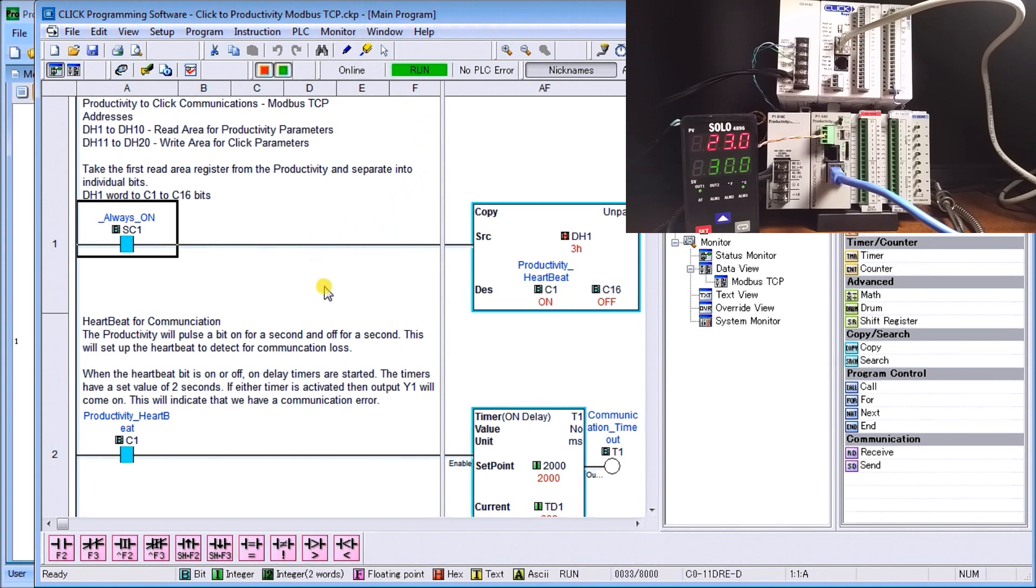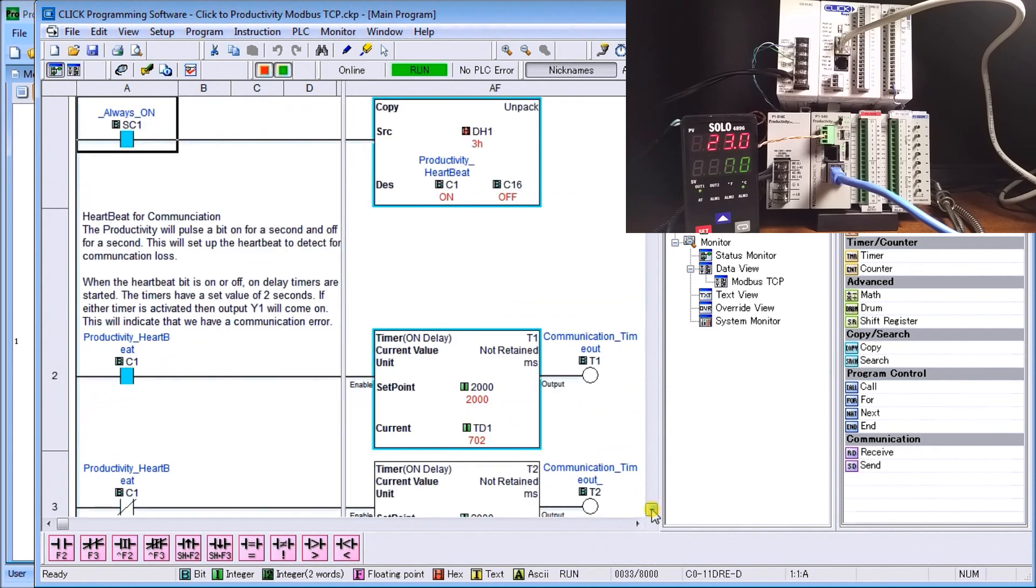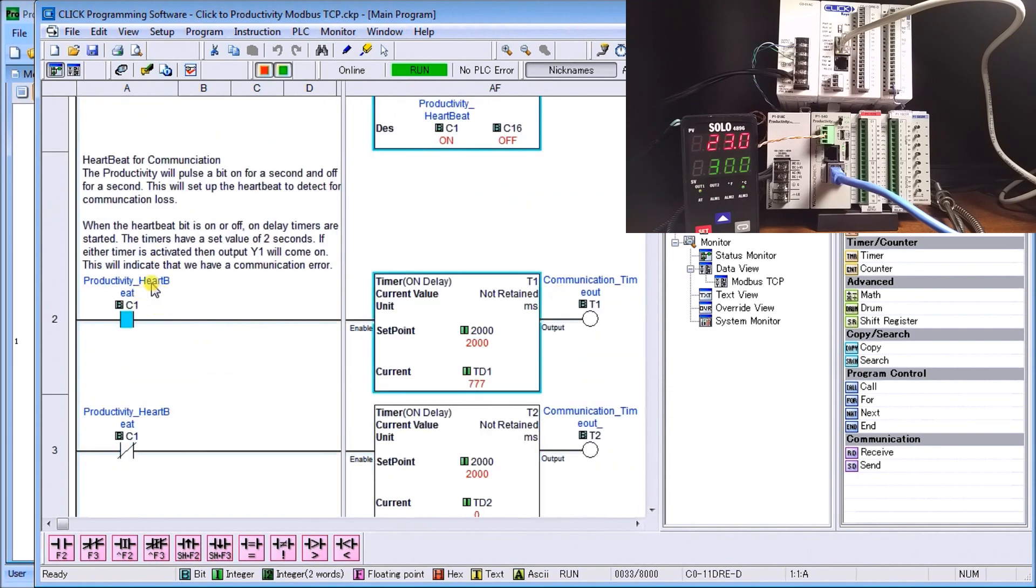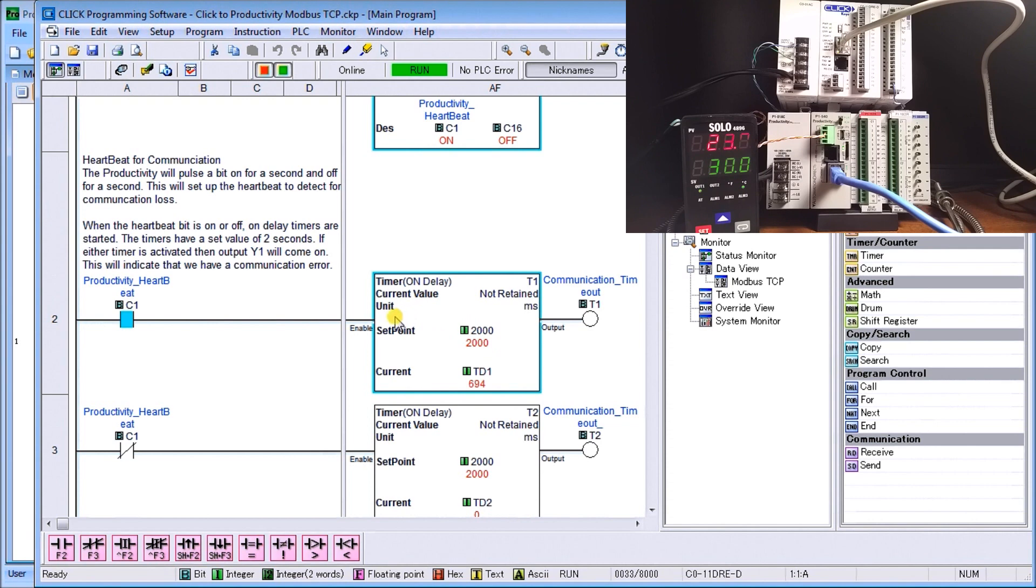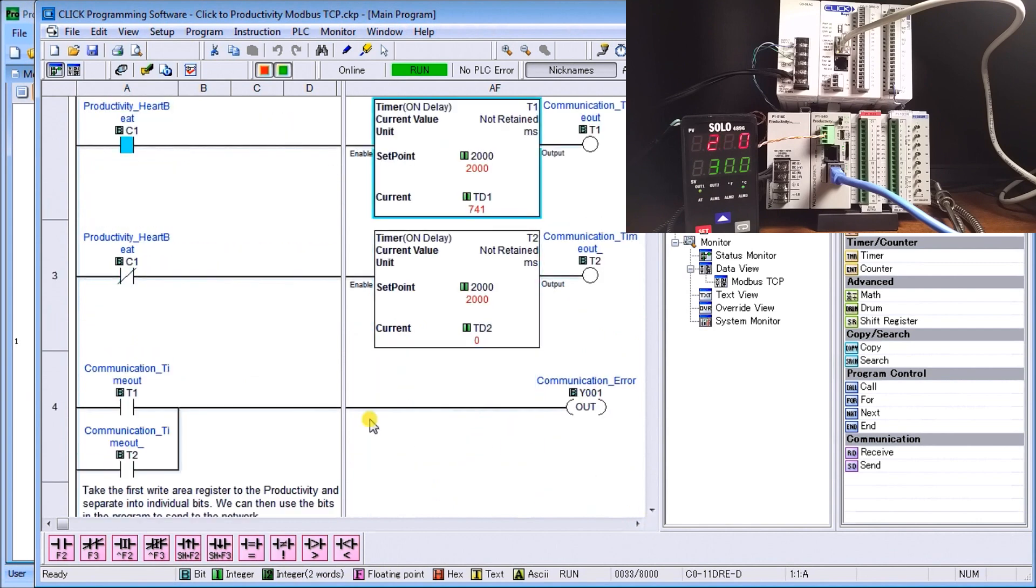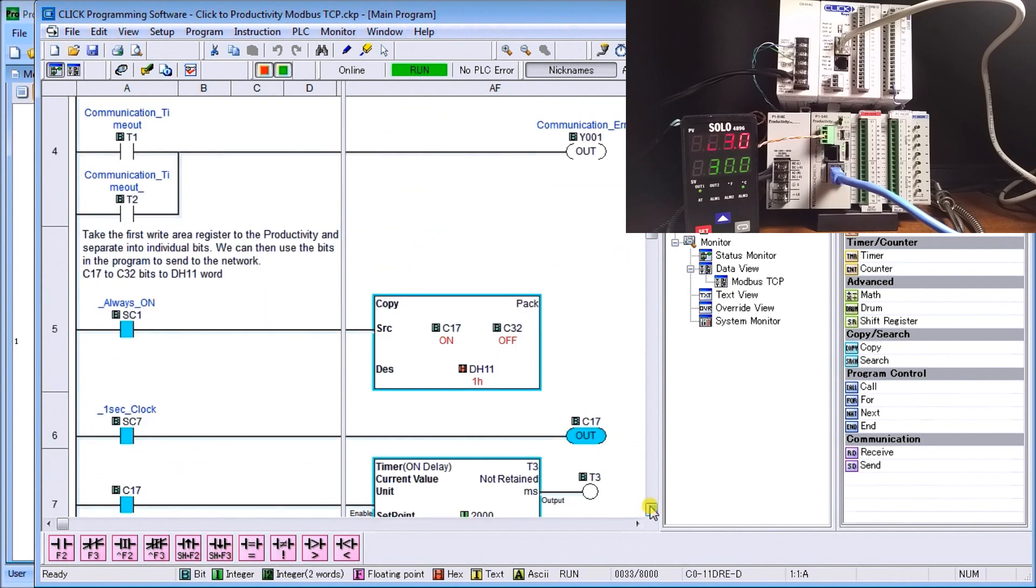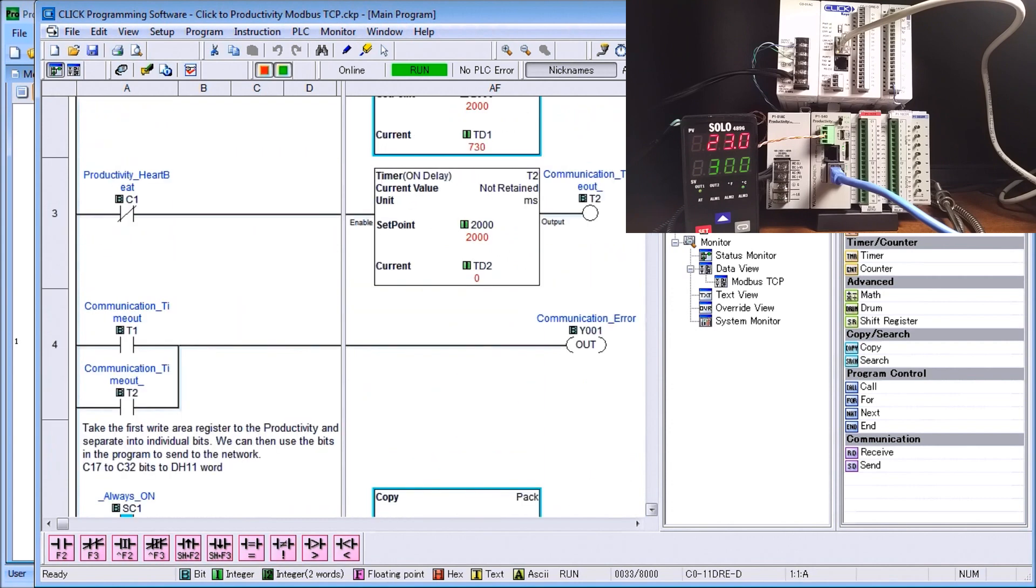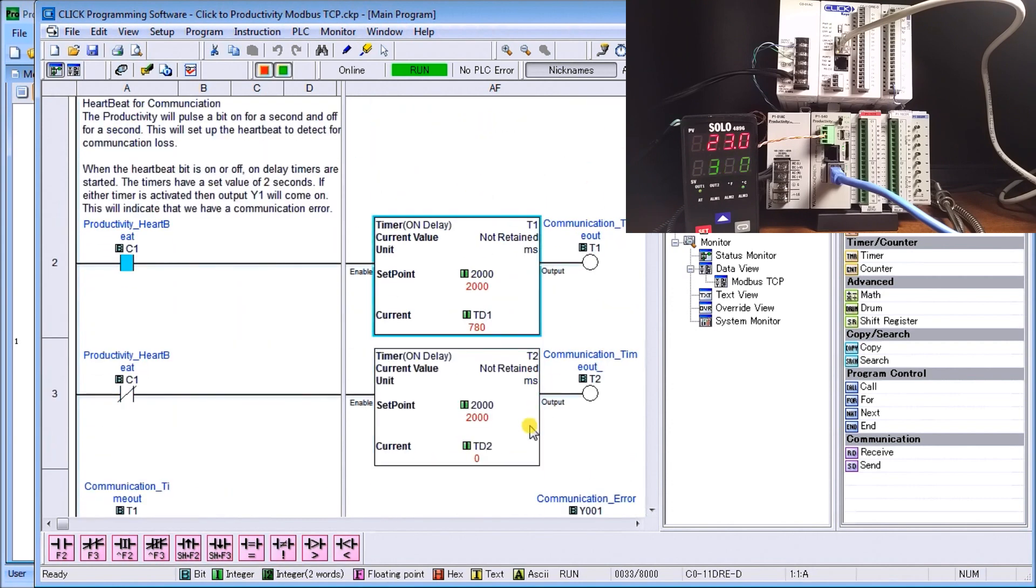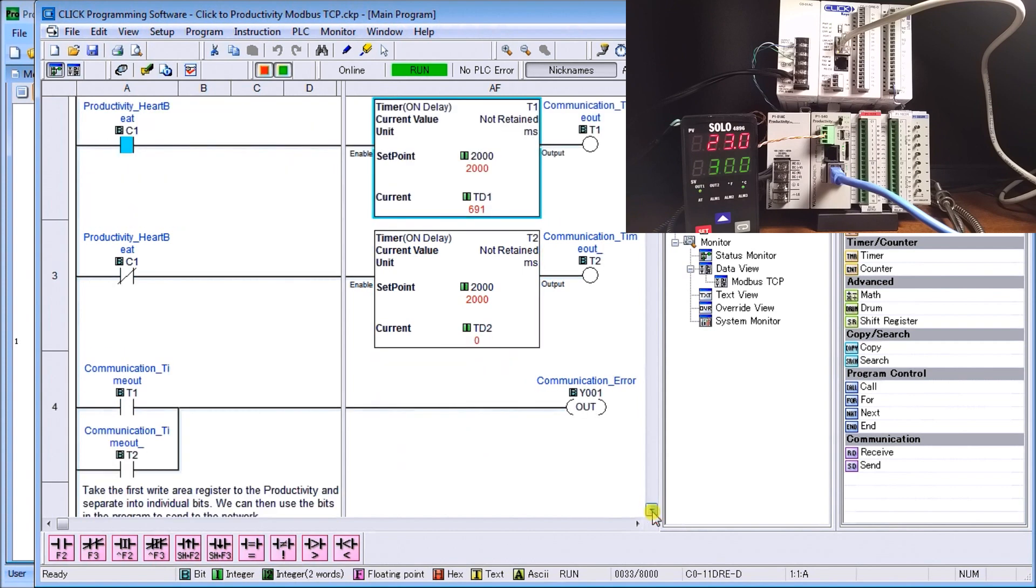The heartbeat takes the very first heartbeat bit, which is C1, and it will start a timer. The timer is set for 2000 milliseconds and you see the current time. As the heartbeat goes on for a second, off for a second, it will indicate the time. Then what we do is when a timeout bit happens after the two seconds, if it's on or off for that long time, it will actually activate our communication error flag. That is our communication bit status.